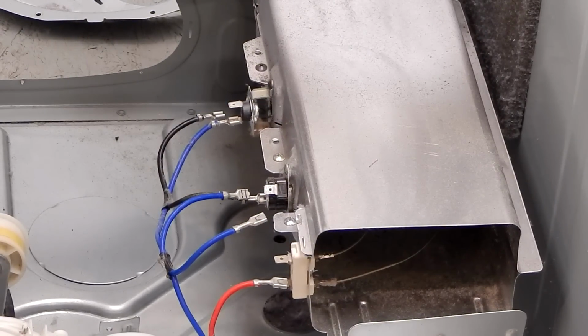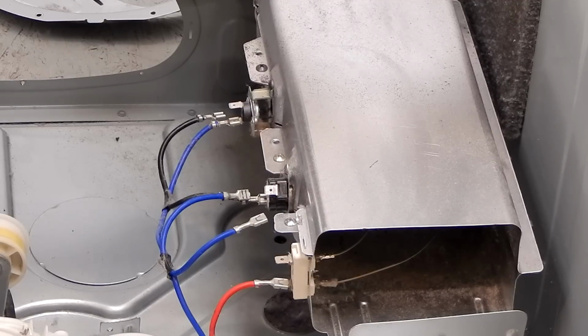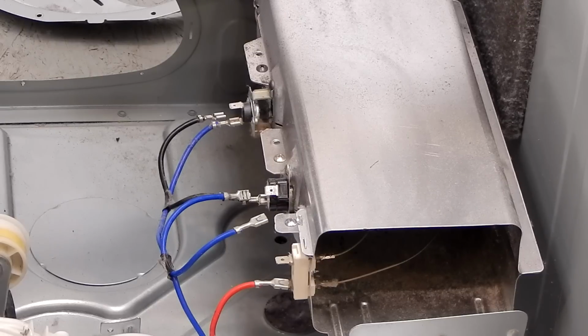Now I went ahead and took one wire off each of the terminals on the components there. Of course the red and the blue wire up front there go to the heating element itself. The next thermostat back is the high limit, and the little one behind that is your thermal cutoff. Now I'm going to go down there and test those real quick and show you the reading that you're going to get on those.